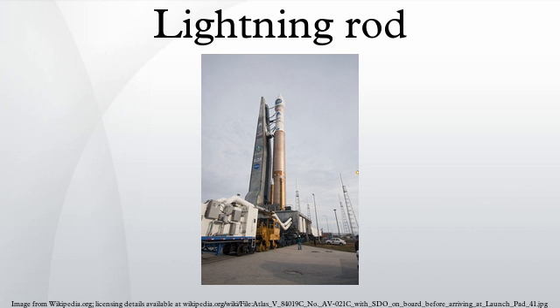Protection of electric distribution systems. In overhead electric transmission systems, one or two lighter gauge conductors may be mounted to the top of the pylons, poles, or towers not specifically used to send electricity through the grid. These conductors, often referred to as static, pilot, or shield wires, are designed to be the point of lightning termination instead of the high-voltage lines themselves. These conductors are intended to protect the primary power conductors from lightning strikes.